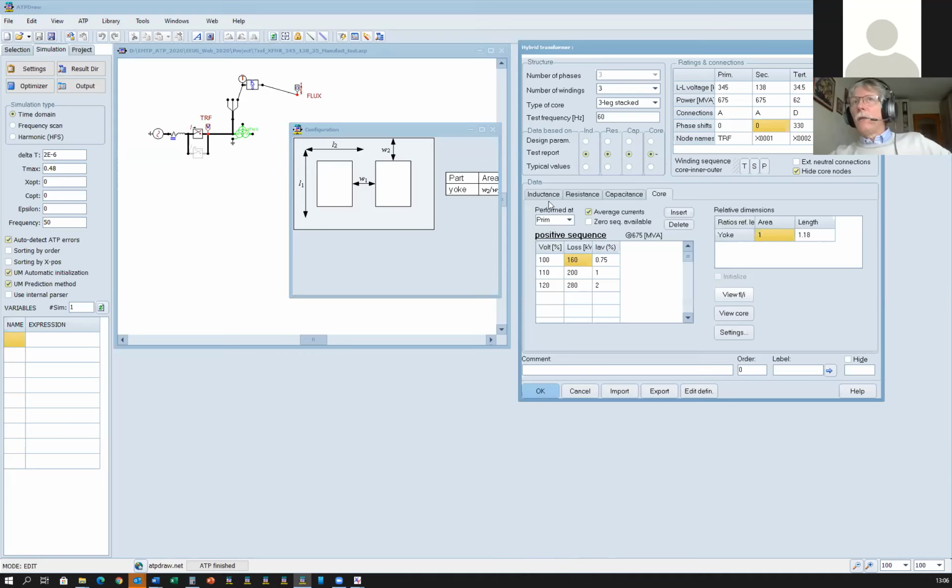And this way, you can see very similar windows as for the BCTRAN. If you wish, you can even omit the capacitances completely. It is also not well known that if you right-click, you can switch off the capacitance option completely. So in that case, the hybrid model will work without capacitances. If you don't have them, you can choose typical values and you will have some capacitances there.